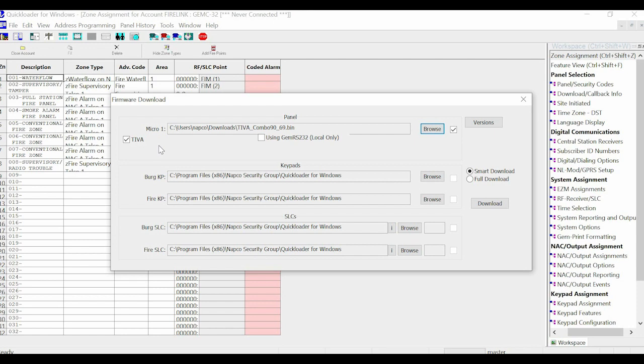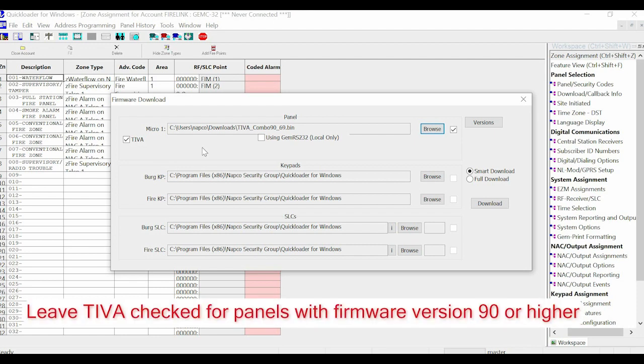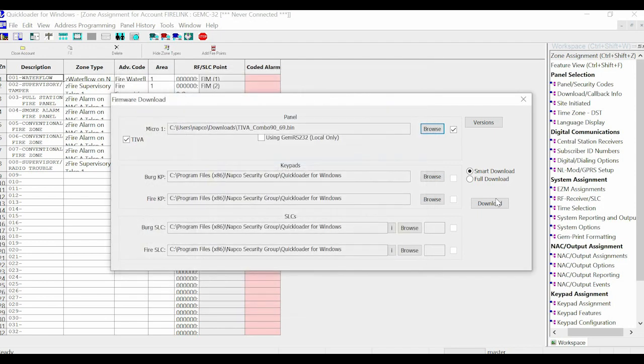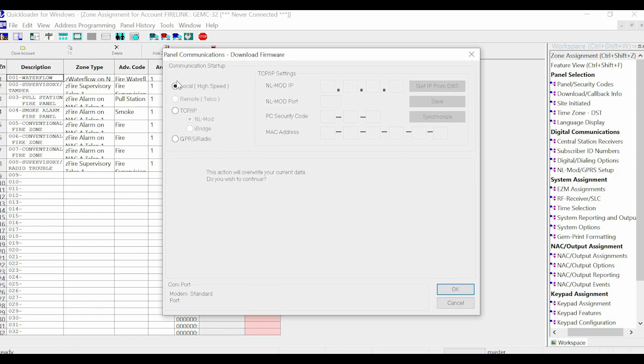If you have a panel with TIVA firmware, which would start with 90 dot whatever the version, we would leave this checked, click Browse, pick the correct version, and then click Download to Panel. We would pick local, radio, whatever mode we're going to use.